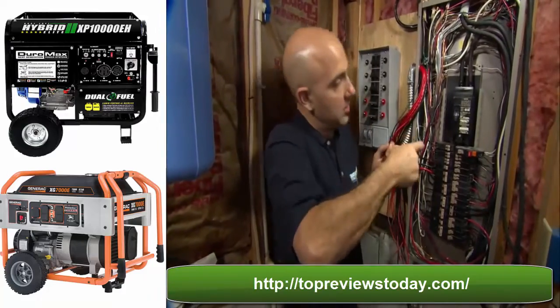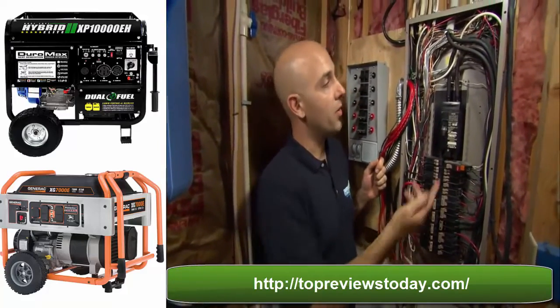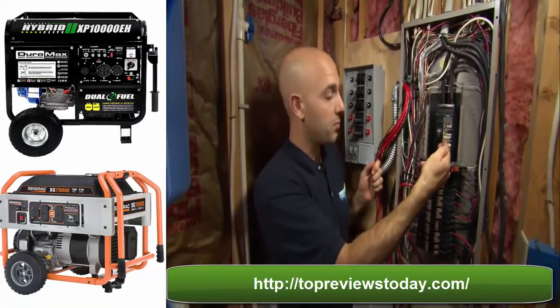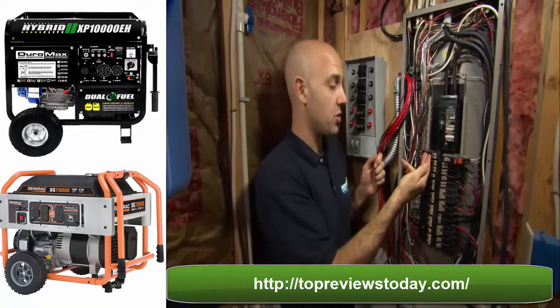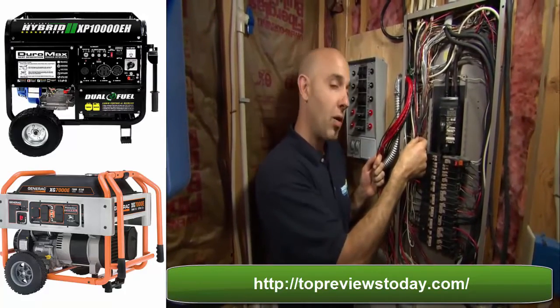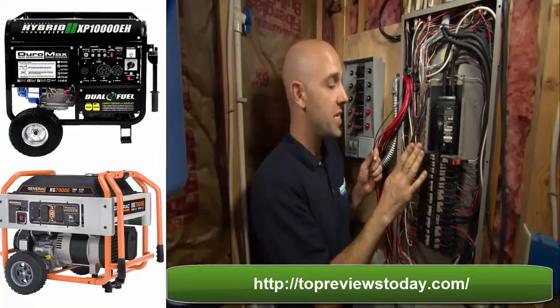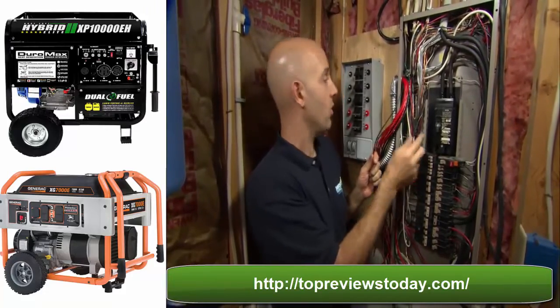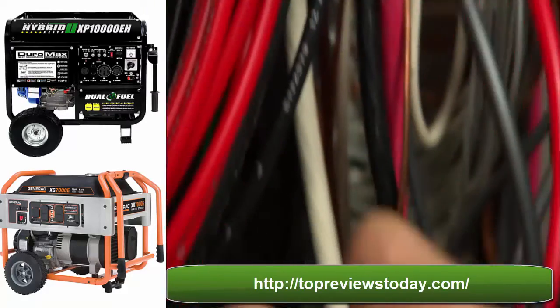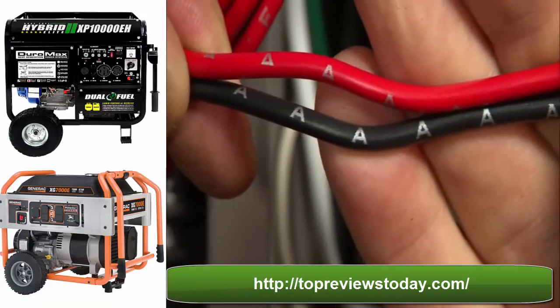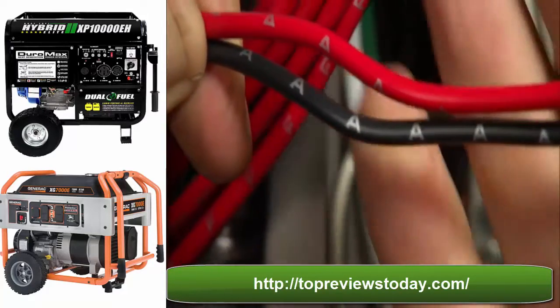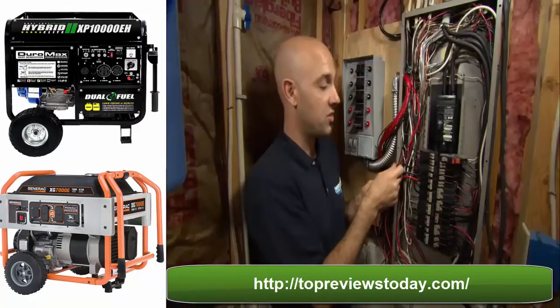Okay, now Chris, right now the utility power travels in through the main circuit breaker, out through this branch circuit breaker, up this black wire to your kitchen lighting. What we need to do is interrupt this wire with the transfer switch. So they provide us 2 wires, a red and a black, and they both have a letter on them which corresponds to the switch on the transfer switch.